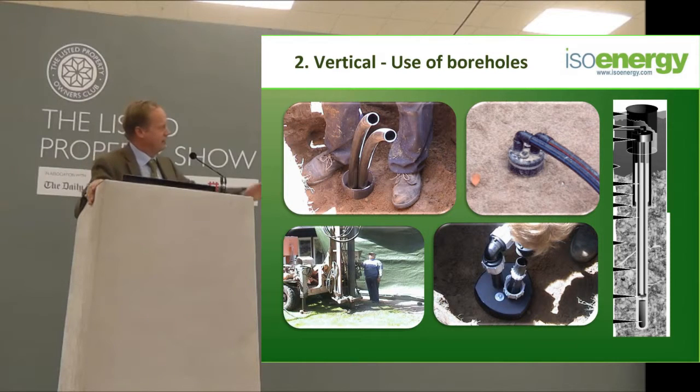You can see here on the right a borehole going down normally about a hundred metres. One important issue: if you're doing pipework in the field or down a borehole, don't use joints that are screwed together by hand, and don't use push-fit pressure joints — only weld. Screwed joints will fail over the years, and believe me, it is not easy to locate where that borehole was five, ten, or fifteen years later. The welded joint shown at top right is as good as the permanent pipe.